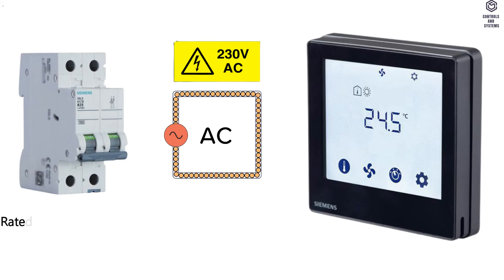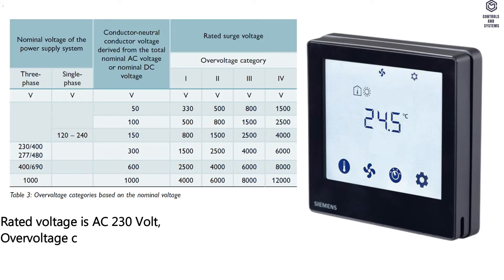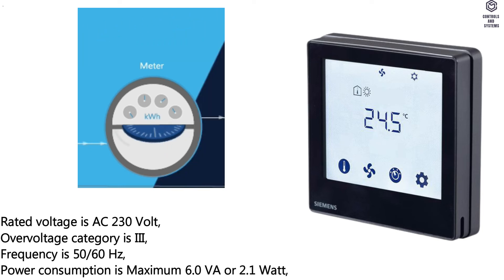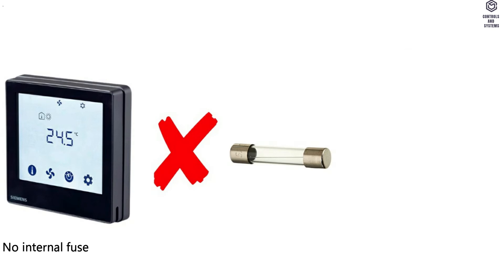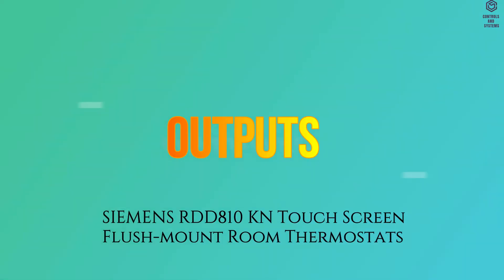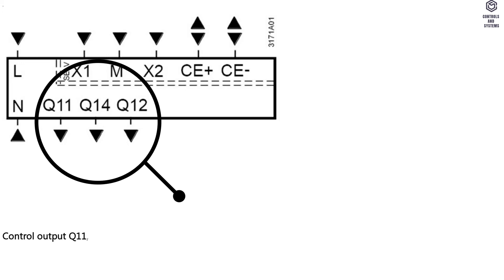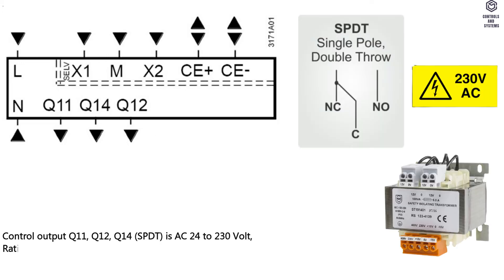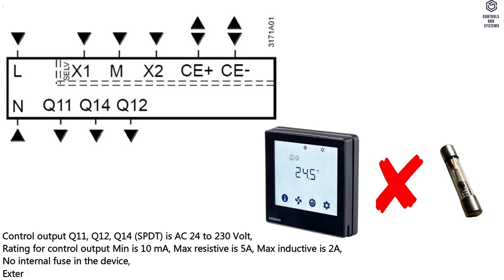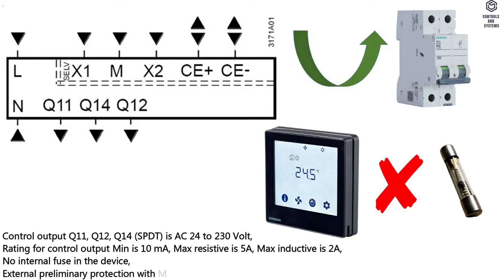Electrical Data: rated voltage AC 230V, overvoltage category 3, frequency 50 or 60 Hz, power consumption maximum 6.0 VA or 2.1 W. No internal fuse in the device; external preliminary protection with maximum C10A circuit breaker in the supply line. Q11, Q12, Q14 SPDT: AC 24 to 230V. Rating for control output: minimum 10 mA, maximum resistive 5A, maximum inductive 2A. No internal fuse; external preliminary protection with maximum C10A circuit breaker in the supply line Q11 required in all cases.